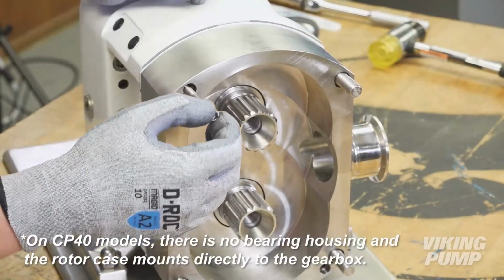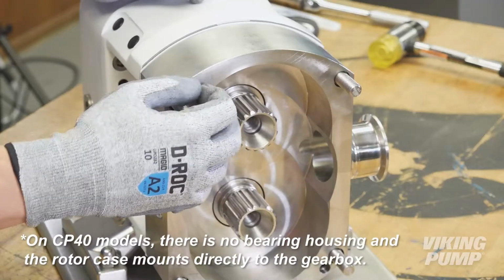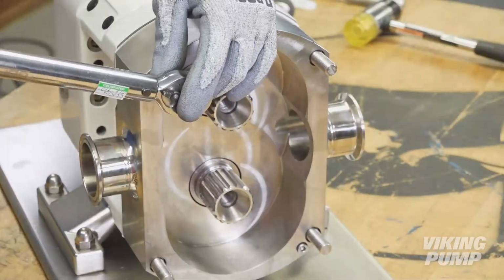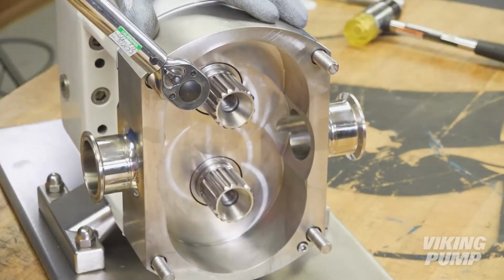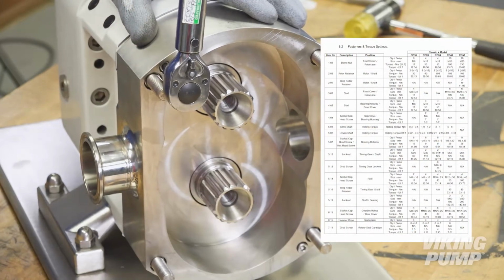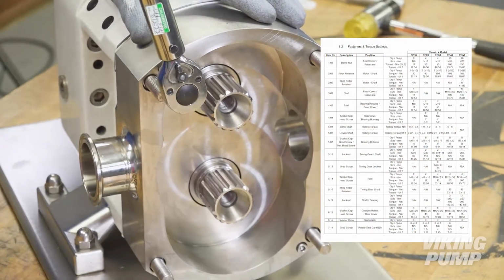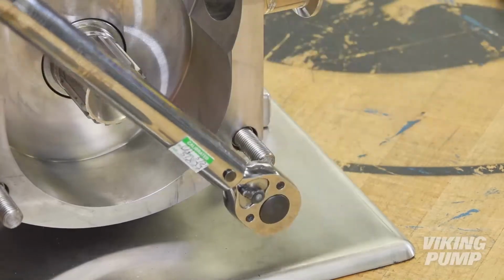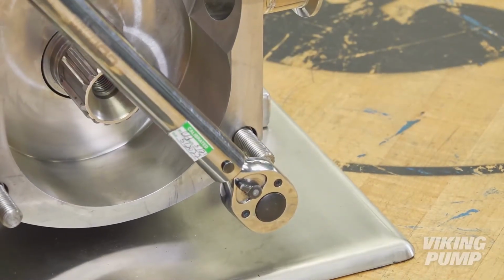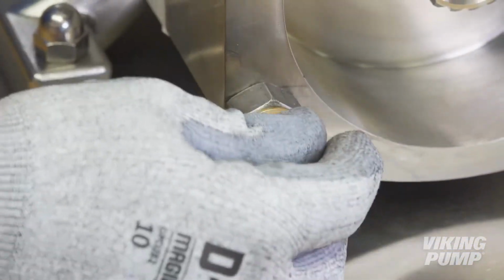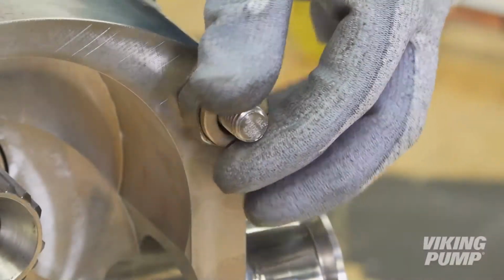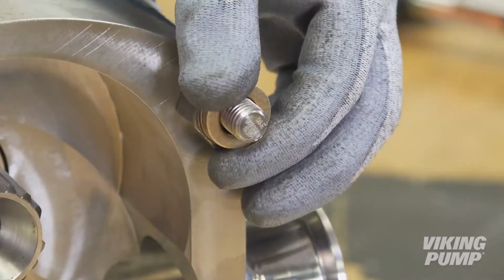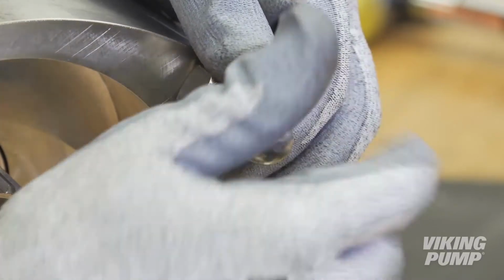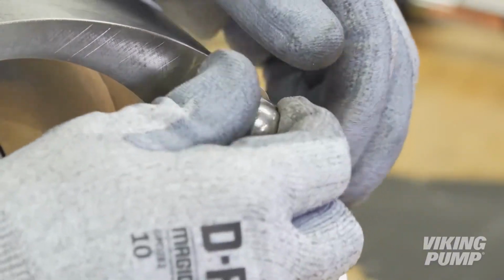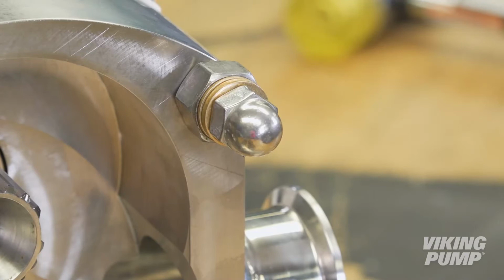For CP20 and CP30 models, the rotor case can now be secured using the socket head cap screws. Torque to the appropriate setting. This setting can be found in the service manual. Secure the opposite corners using spacers and the dome nuts. CP10 models have no rotor case socket head cap screws, so all 4 corners will need to be temporarily secured using this method. This clamping is necessary for checking the clearances later.